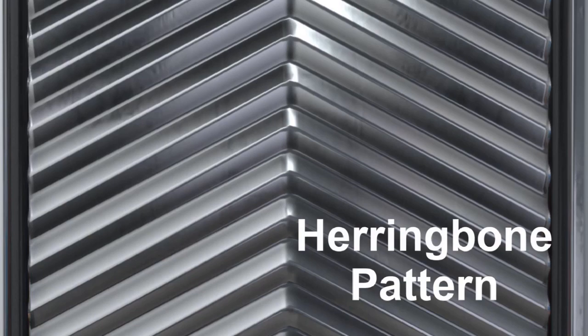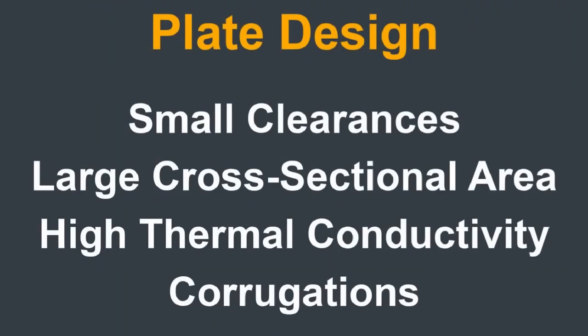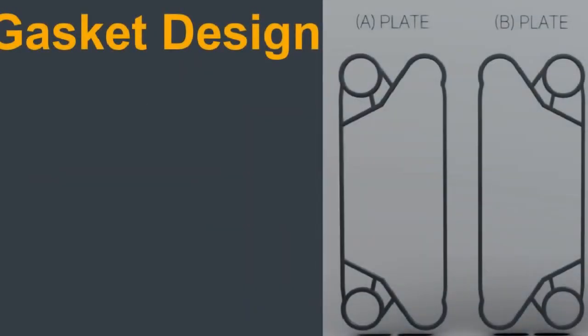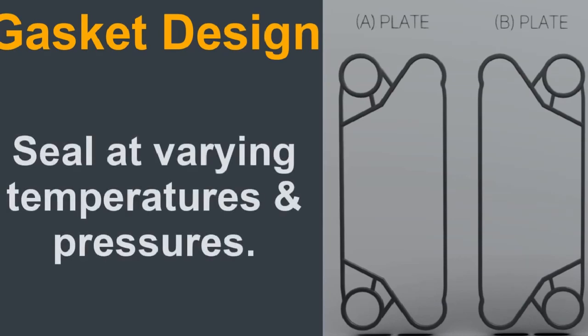So although the plates look simple, a lot of engineering was applied to their design. But the plates are not the only part of a plate heat exchanger with extensive design features. Take the gaskets for example. The gaskets are able to maintain a seal between the plates even when the system pressure and temperature varies.